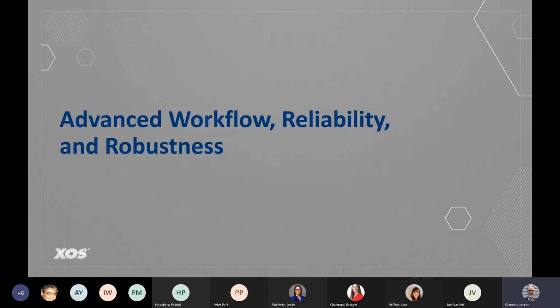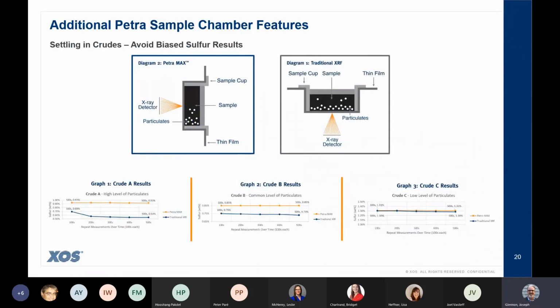Workflow reliability and robustness, a little more into that. In addition, that sample chamber in the vertical is very helpful for things like settling in crudes. So you can see in the diagram on the right, which is diagram 1, with traditional horizontal placement of the sample, settling of particulates is in the way to some degree of the X-ray detector. On the left with the vertical, the particulates settle down and the detector is picking up a clear signal through the sample. You don't have that interference.